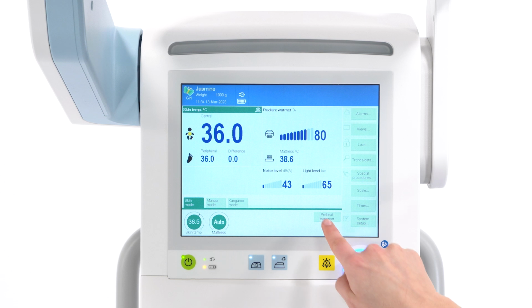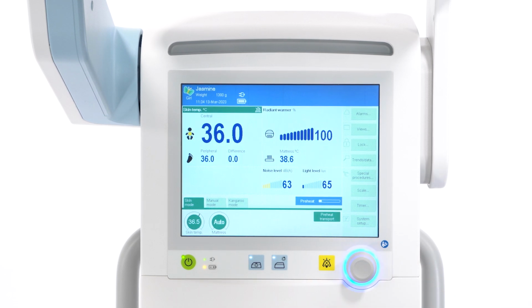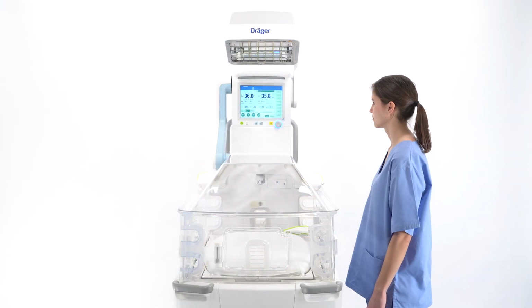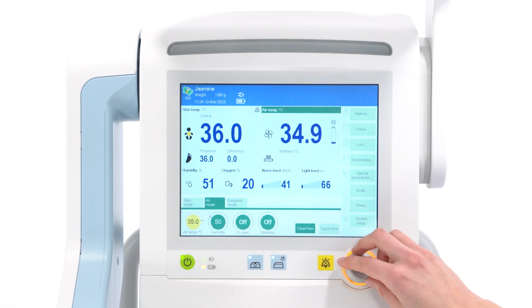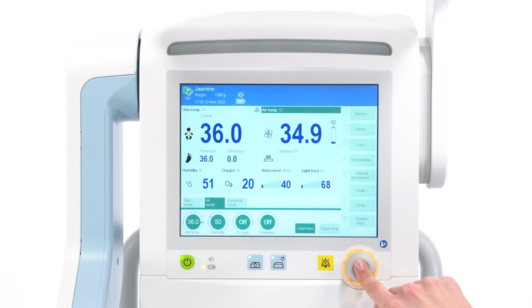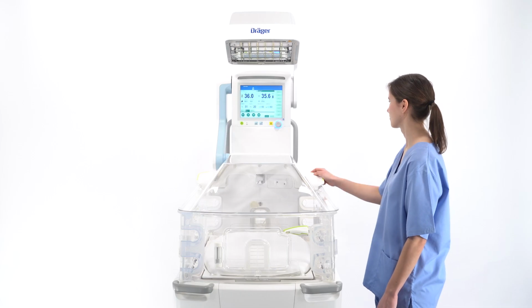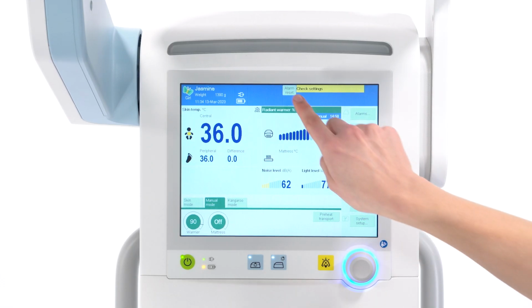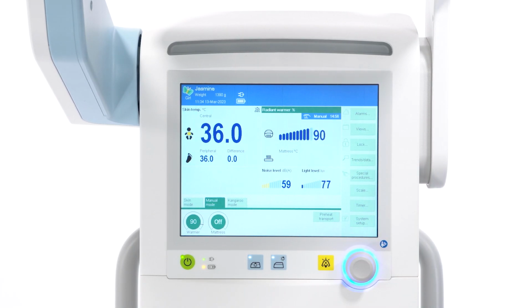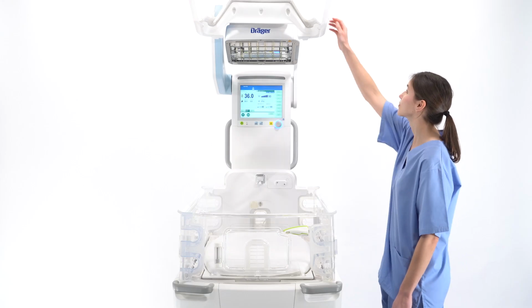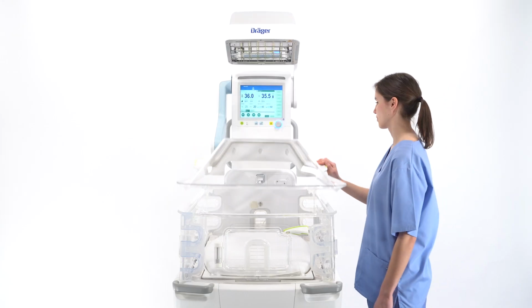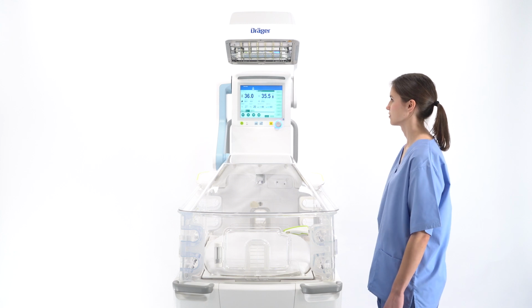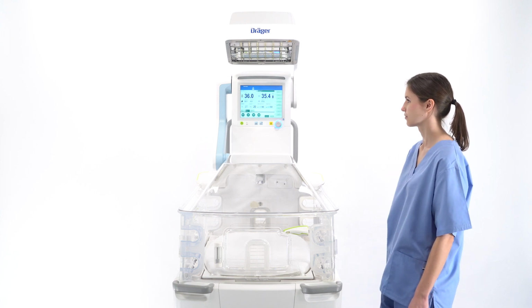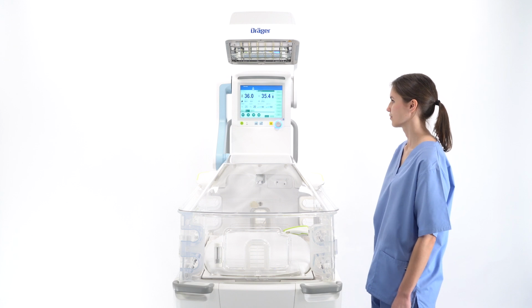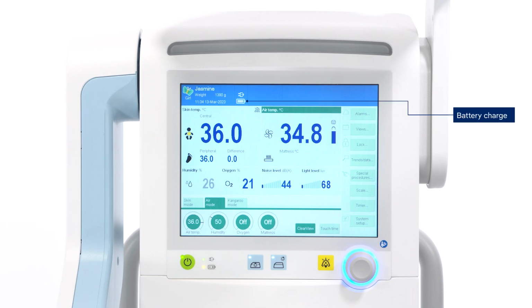Preheat for transport can be used in skin mode. The 2-hour rule can be used to prepare the transport temperature. When the hood is closed, set the air target temperature for later transport. Open the hood for initial patient care. When finished, close the hood again, and the most recent air temperature settings for incubator operation will be applied. When the measured air temperature equals the set target value, incubator transport can be initiated. Make sure the battery charge is sufficient for the transport time required.